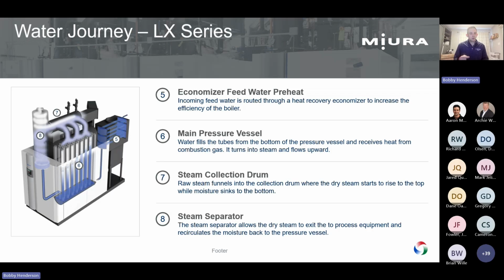So the water journey is going just the opposite way, right? We're bringing our feed water through our economizers, down to the bottom into our mud barrel, going up through our once through steam water tubes. Then we've got a steam collector and steam dryer right there at the end, so we have nice, clean, dry steam coming out of the unit.